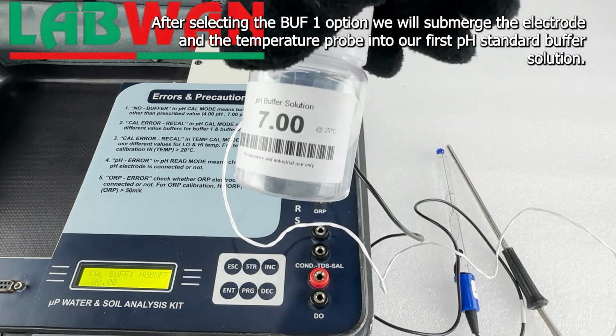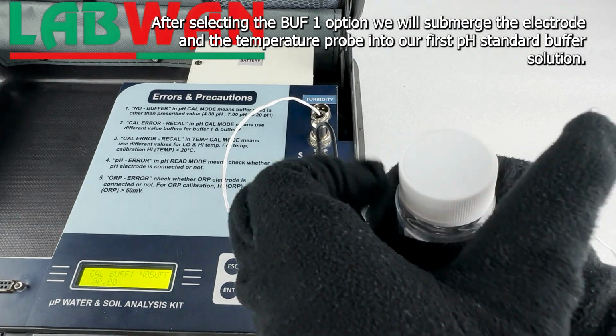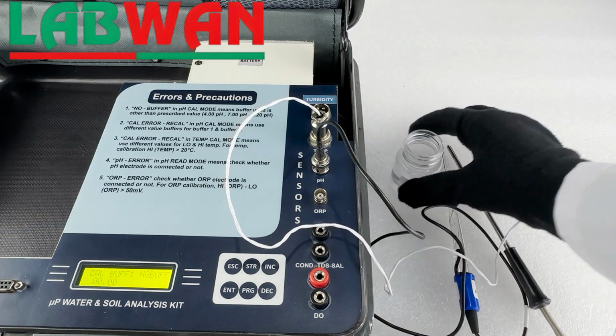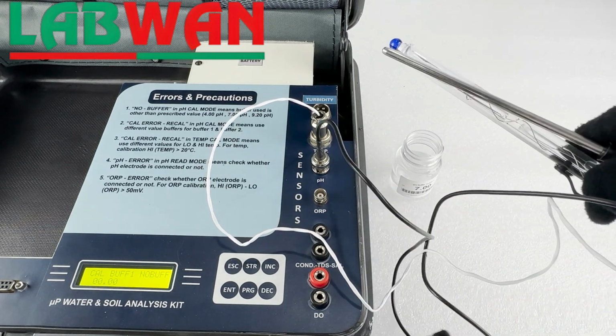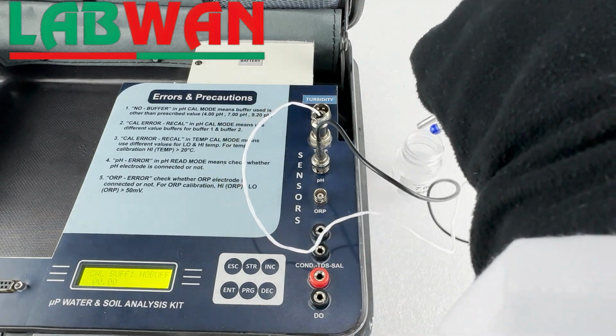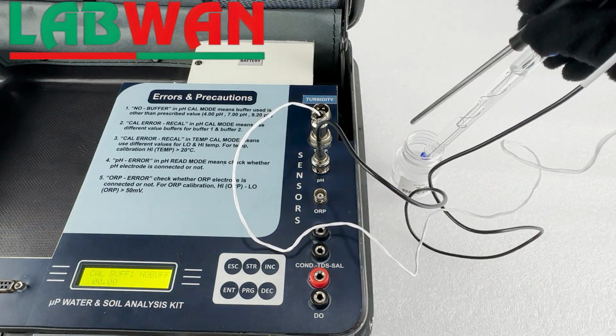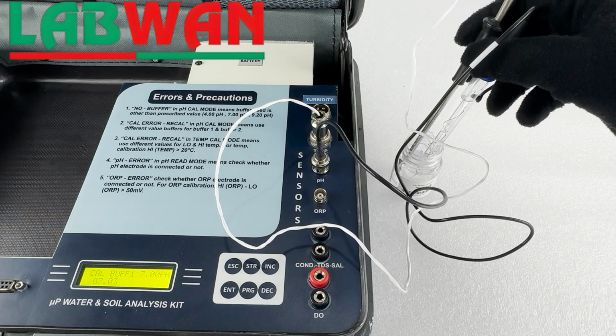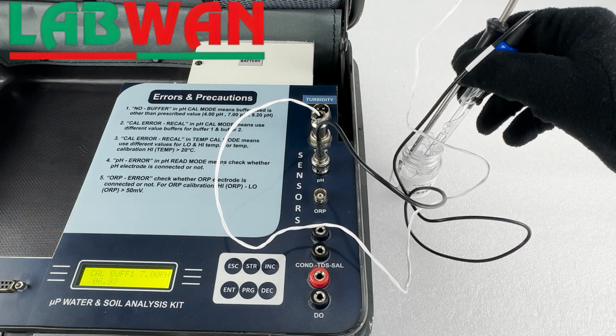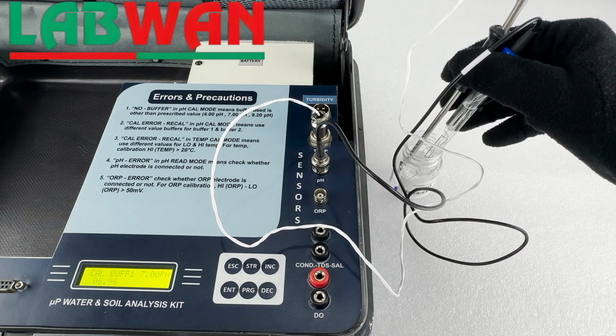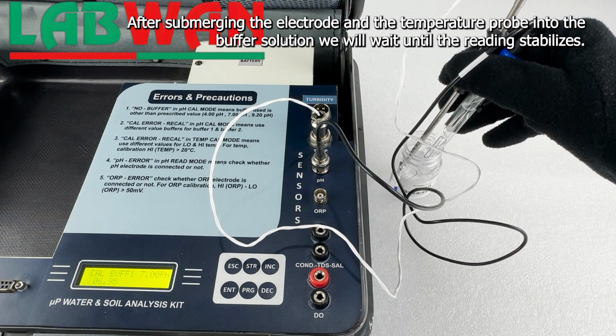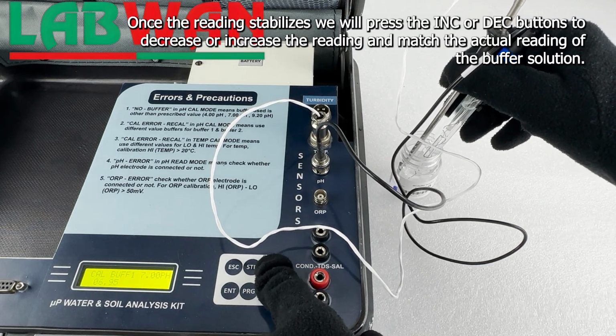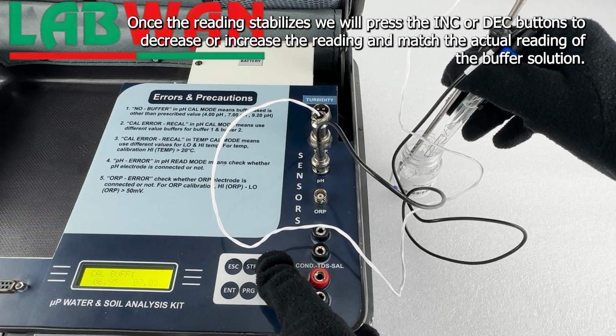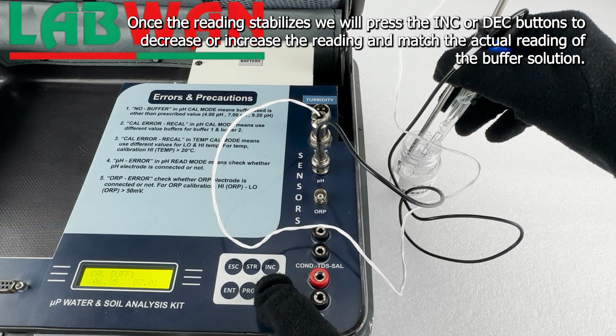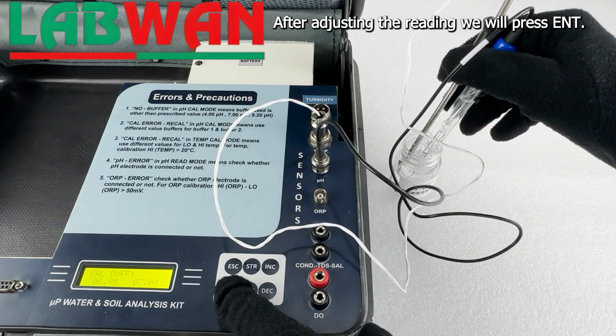After selecting the BUF1 option we will submerge the electrode and the temperature probe into our first pH standard buffer solution. After submerging the electrode and the temperature probe into the buffer solution we will wait until the reading stabilizes. Once the reading stabilizes, we will press the INC or DEC buttons, to decrease or increase the reading and match the actual reading of the buffer solution. After adjusting the reading we will press ENT.